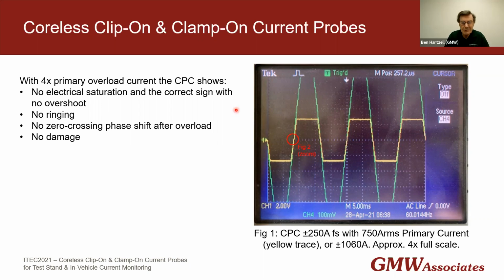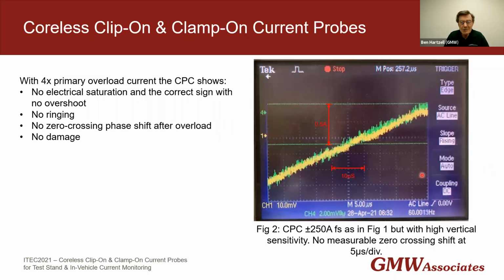So if we blow that up, just this region here, so we can look more at the zero crossing behavior, we now have a 1 microsecond, about 0.5 amps. And remember, this is a 250 amp sensor. And you can see the green is the reference, the yellow is the CPC. And you can see that there's essentially no crossover shift. So the phase is maintained, even though the current probe was overloaded by a factor of 3. And there's also no damage. It can be operated continuously in overload, and there's no damage.